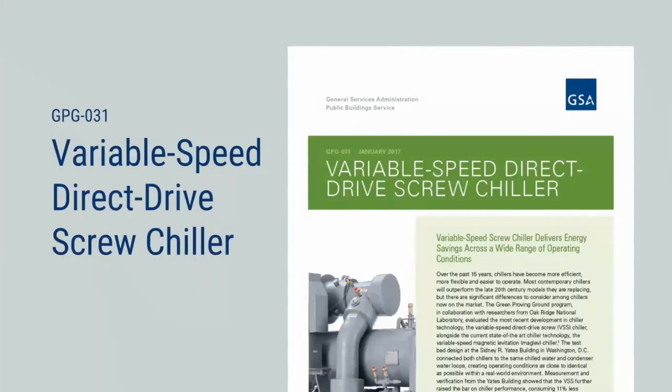This evaluation occurred at the Sidney Yates building in Washington, D.C. in 2015 and 16. The building had recently been renovated, and the chiller plant was about to undergo a major overhaul, replacing two older centrifugal chillers. As part of this overhaul, GSA chose to install a 275-ton variable speed screw chiller in parallel with a 275-ton magnetic bearing centrifugal chiller. The magnetic bearing chiller is of the same type evaluated in the previous GSA study and is widely accepted by the agency. Both units will be connected to the same chilled water and condenser water loops. This configuration allowed GSA to evaluate their performance under near identical operating conditions.